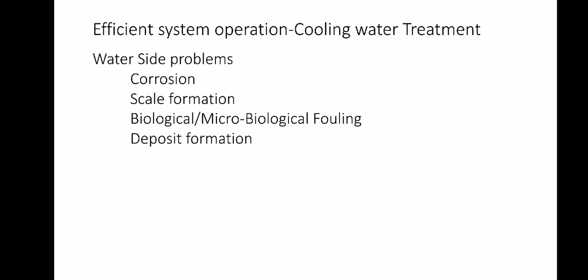Algae obviously block the nozzles of the cooling tower and thus reduce temperature drop of the tower. Slime masses again are responsible for fouling and deposit formation. Then deposit formation: foreign matter such as turbidity, sand, silt, mud, airborne debris and other suspended impurities are the sources of deposit formation. Corrosion products that are formed also add to the deposit formation.